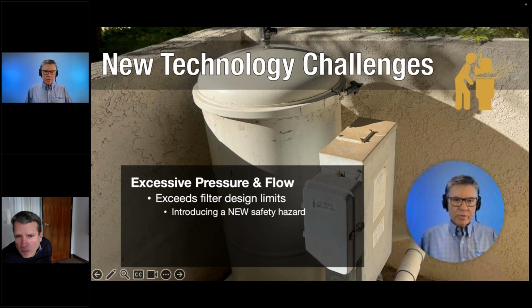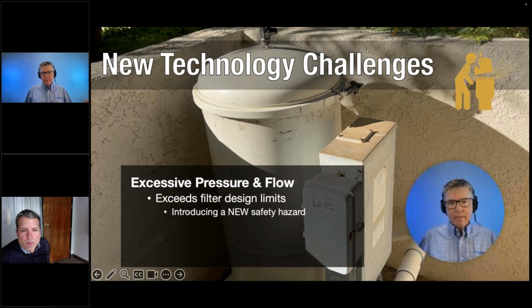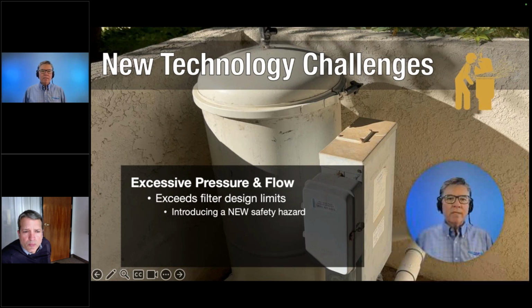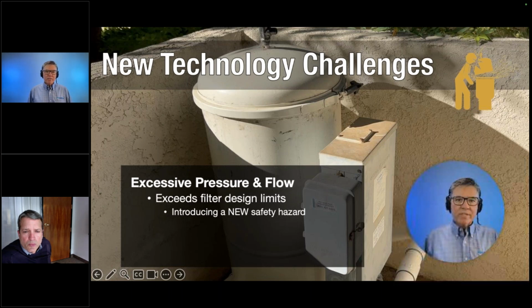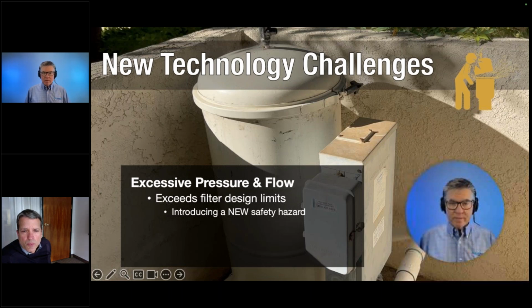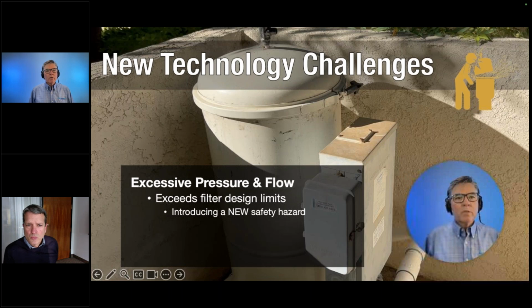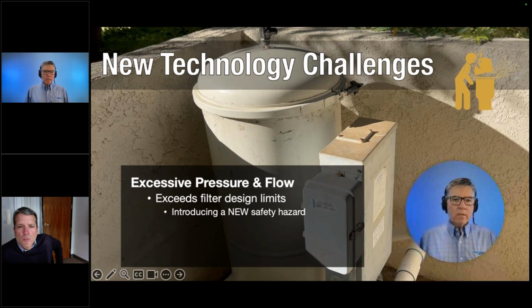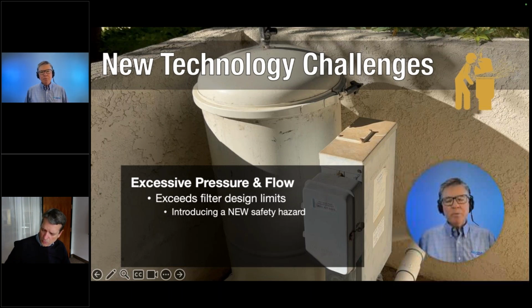the pressure-related failures that we are seeing with old polymer, fiberglass, plastic filter tanks, where you put a new variable speed pump on, and then you get a call 3 or 4 or 5 or 6 weeks later, maybe a few months later, that all of a sudden it's sprung a leak or worse. So when installing variable speed pumps, you have to look at what that pump will be capable of on the pressure side and potentially on the flow. But I'm going to pause on that one because we're going to go into a lot of detail on back pressure and the effects of flow on various variable speed pumps.